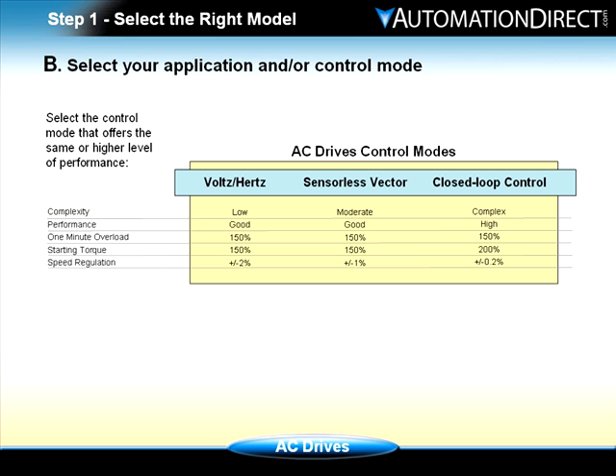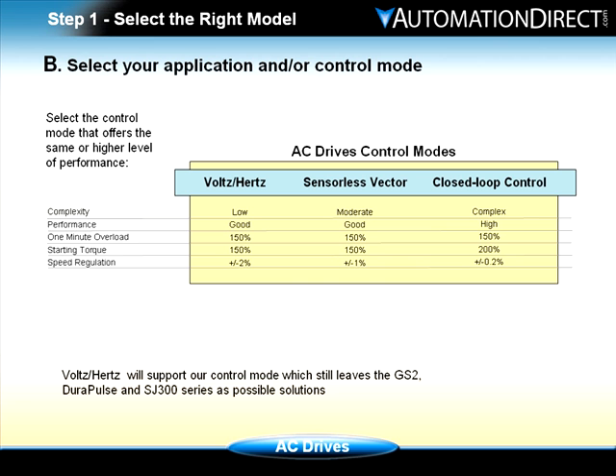There are three control modes available. Volts/Hertz, which is open loop control, takes the speed reference from an external source and varies the voltage and frequency to control the speed of the motor. Sensorless vector, although similar to Volts/Hertz, has internal feedback that monitors reflections from the motor to determine speed. And closed loop, which uses encoder feedback. Volts/Hertz will support our control mode, which still leaves the GS2, DuraPulse, and SJ300 series as possible solutions.